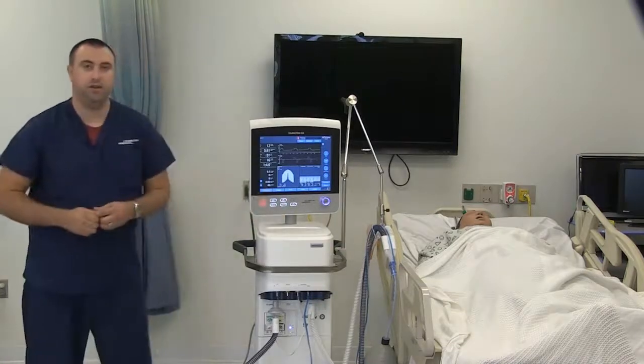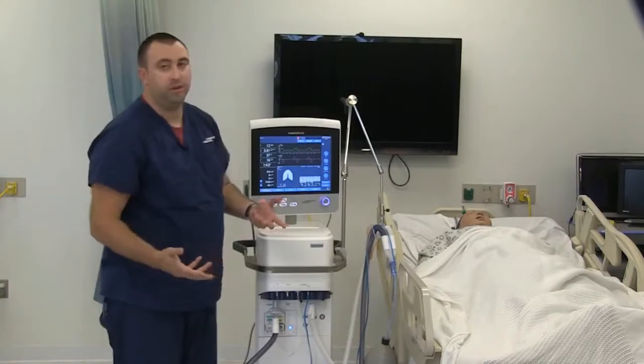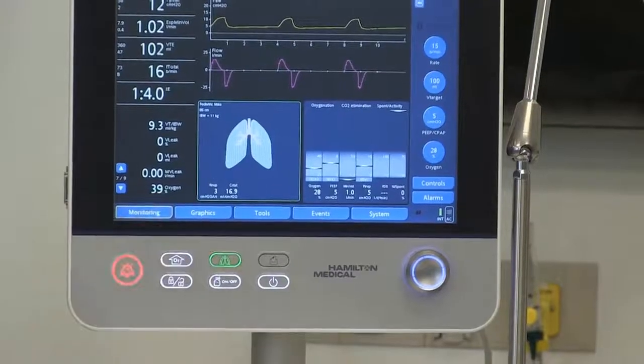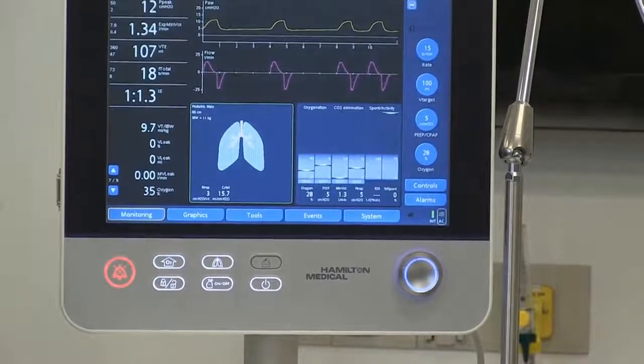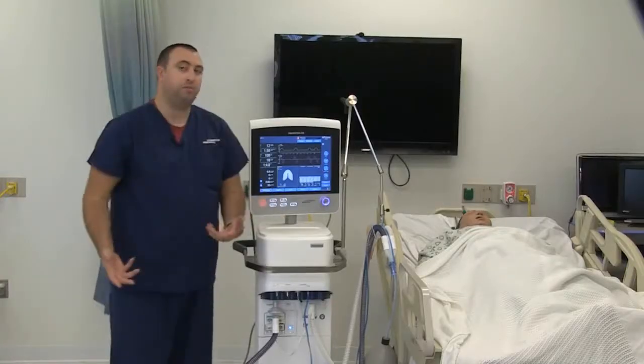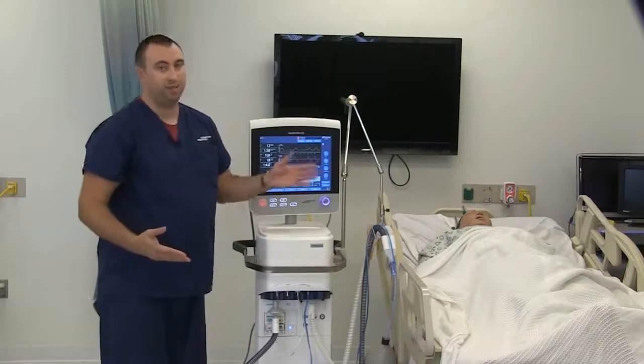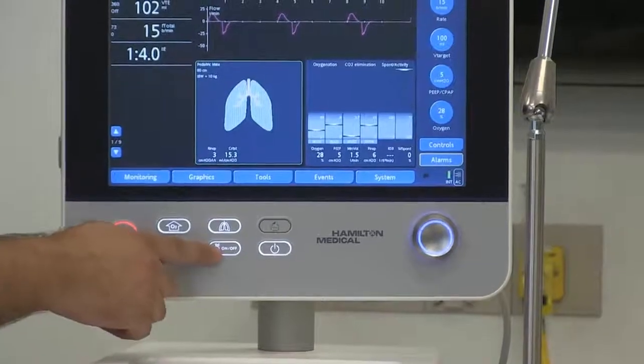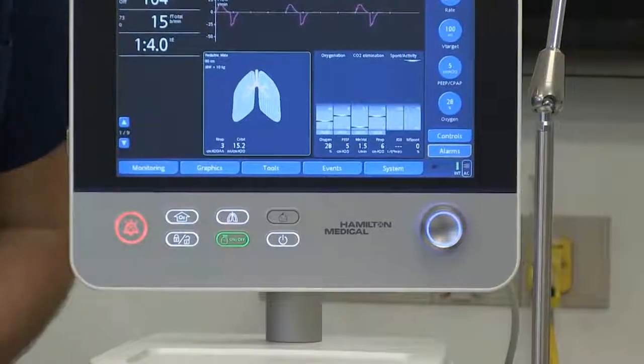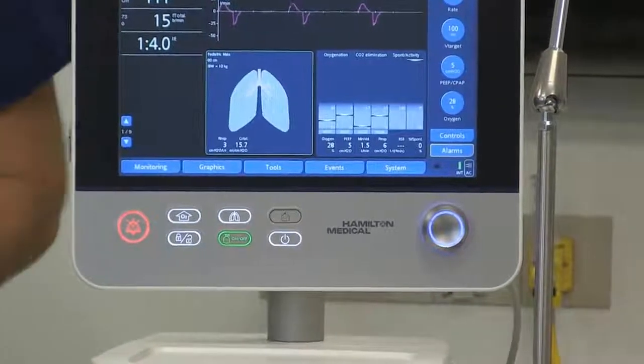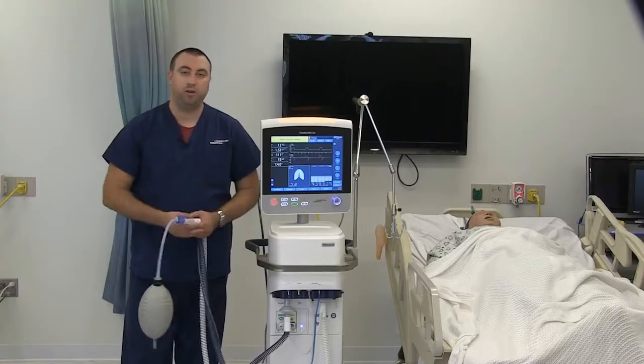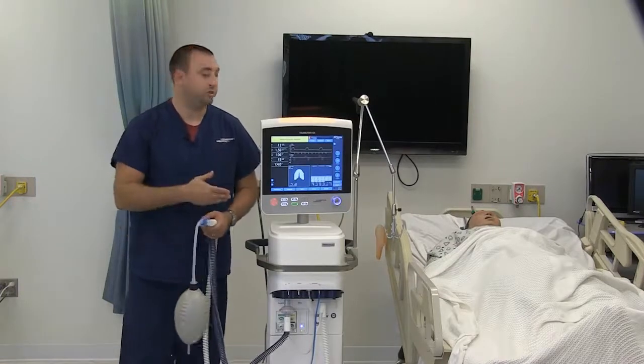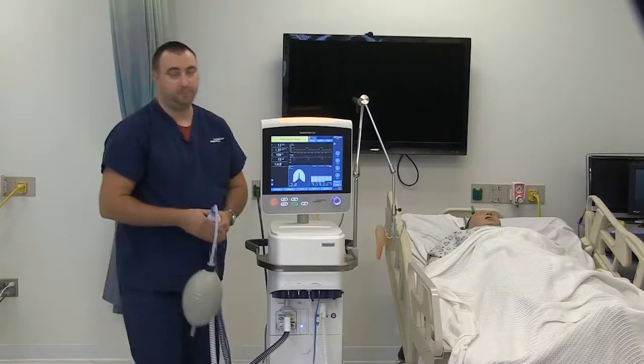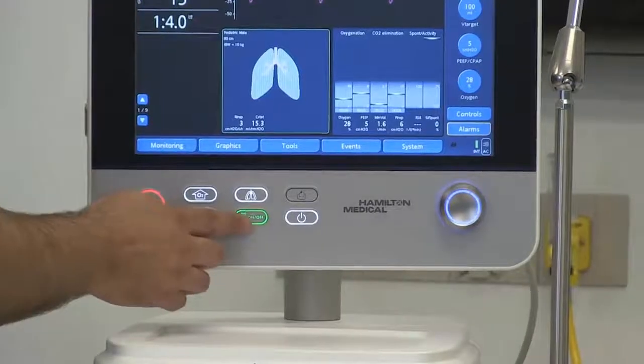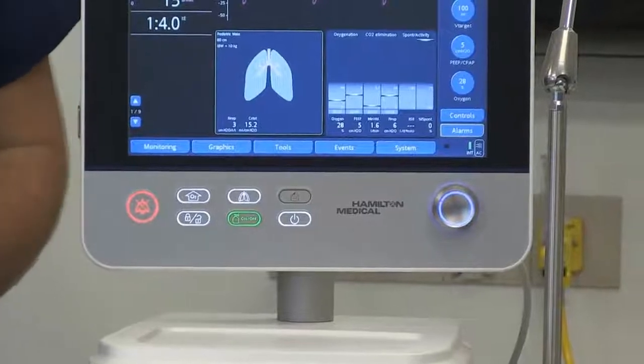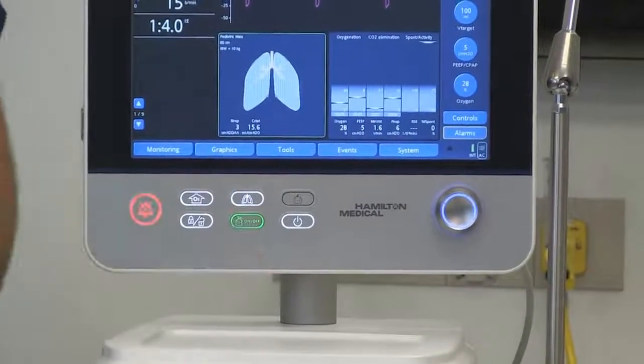Lung button is your manual breath button. If at any point you need to give a manual breath, this will give a manual breath at the settings that you have set. If you hold it down, it will not perform an inspiratory hold. It will simply give the breath with the I-time that you have set. Nebulizer button toggles on and off. When it's toggled on, it will deliver a nebulizer treatment to the patient per the settings that we discussed earlier on in the film. It toggles on and off. If you notice that your nebulizer is finished before it actually toggles off, you can toggle it off here.